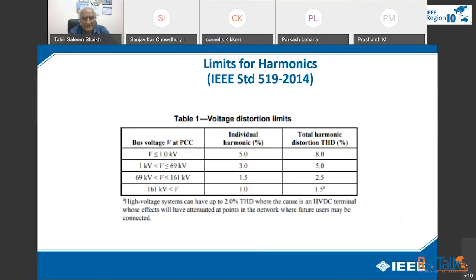Now this is the IEEE standard 519-2014, which gives different voltage levels and the individual harmonic limits. Globally, there are multinational companies that set their limits as per IEEE standards. So for the total voltage harmonics, the limiting value is 5% and the current harmonic is 10%. This is the THD value, which is called the total harmonic distortion.